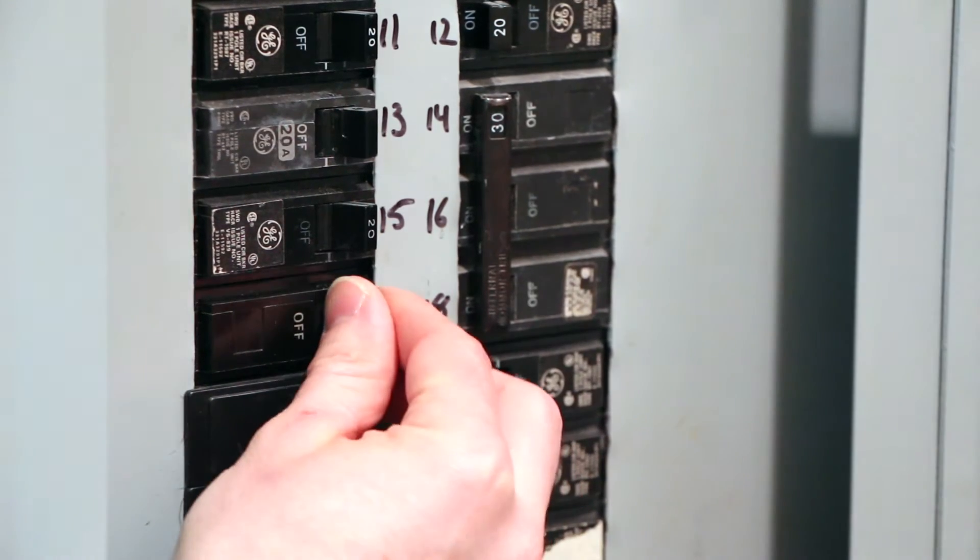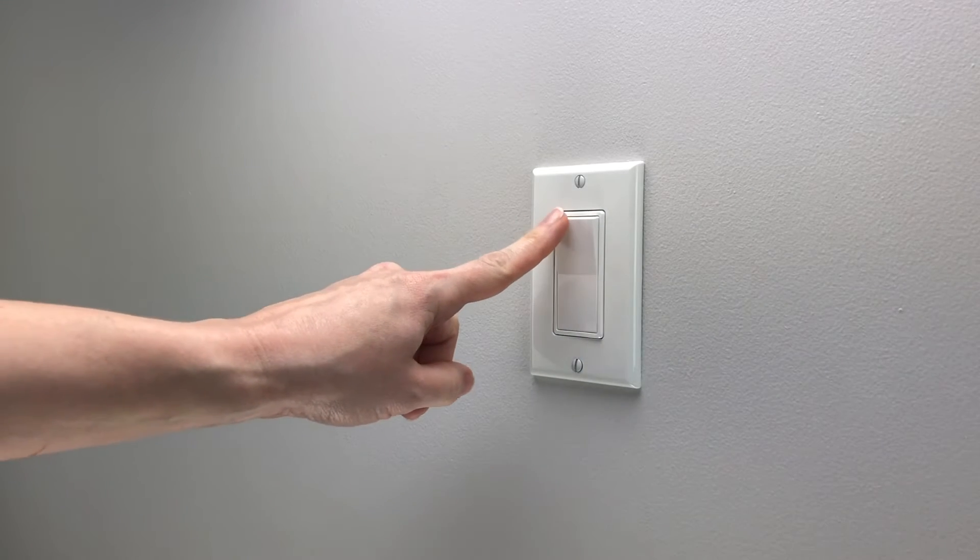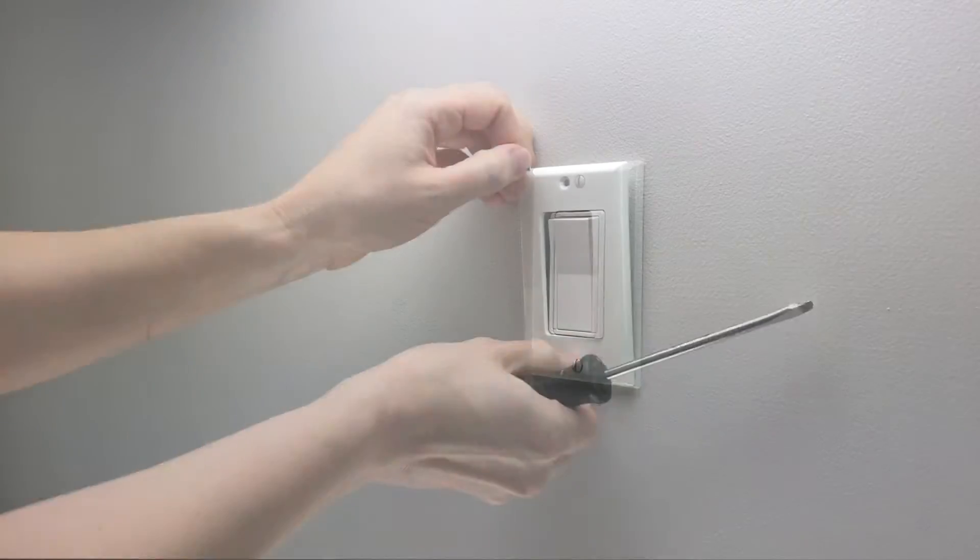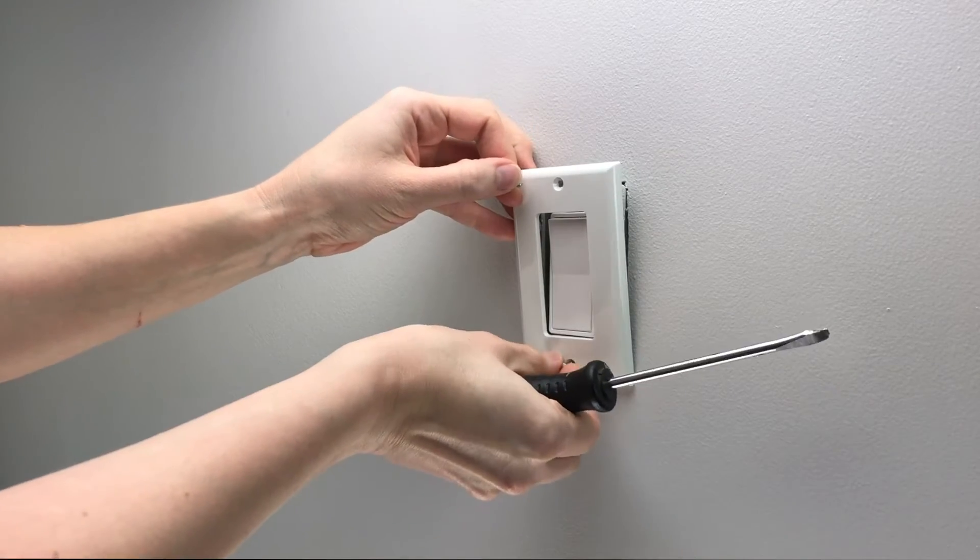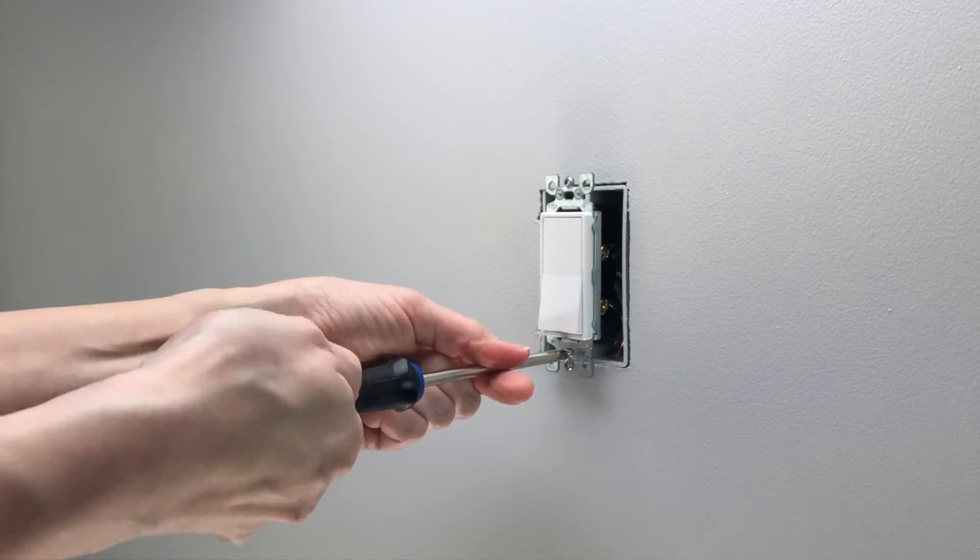Turn off the power at your breaker or fuse panel for the appropriate circuit of your home. Turn the existing light switch on, then off, to confirm the power has been turned off. Remove the existing faceplate, unscrew, and pull the switch carefully out of the gang box.